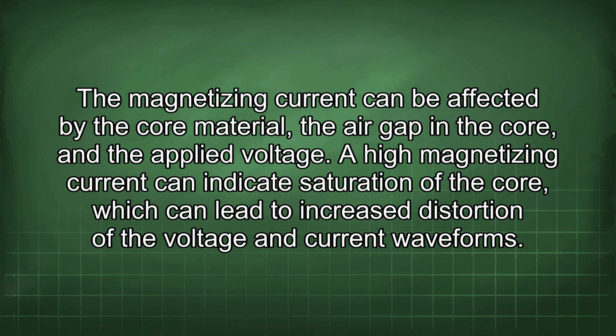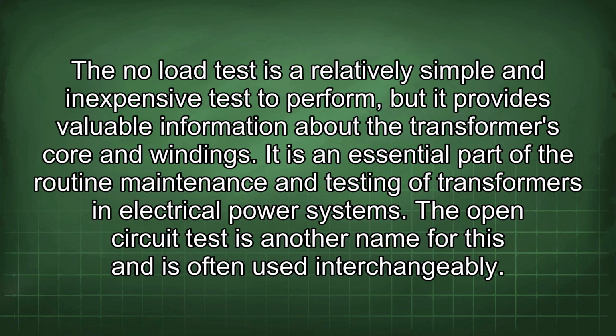A high magnetizing current can indicate saturation of the core, which can lead to increased distortion of the voltage and current waveforms. The no-load test is a relatively simple and inexpensive test to perform, but it provides valuable information about the transformer's core and windings.